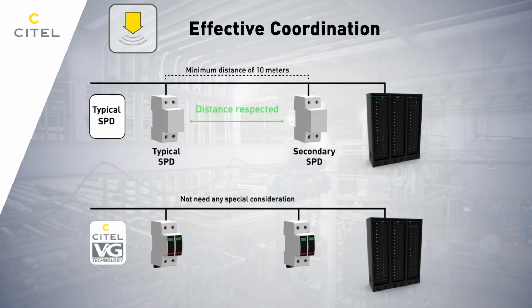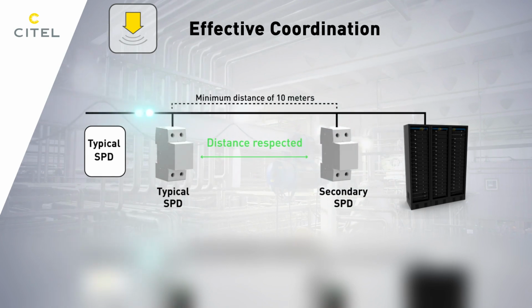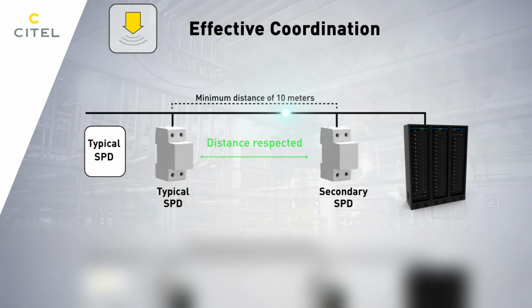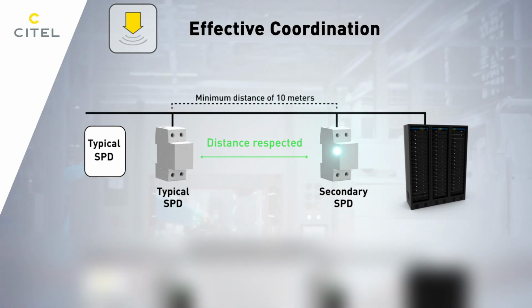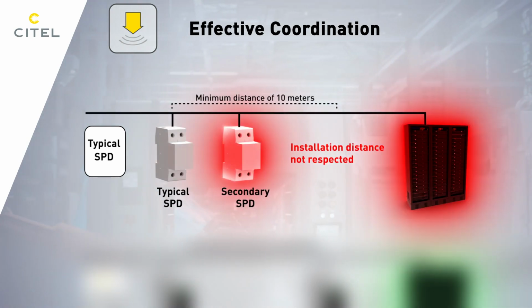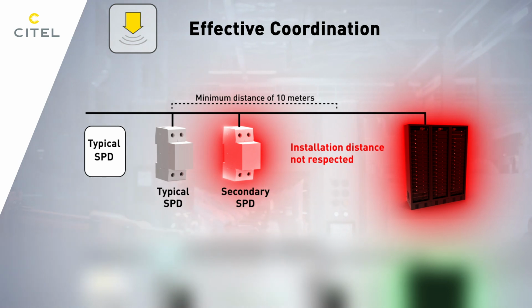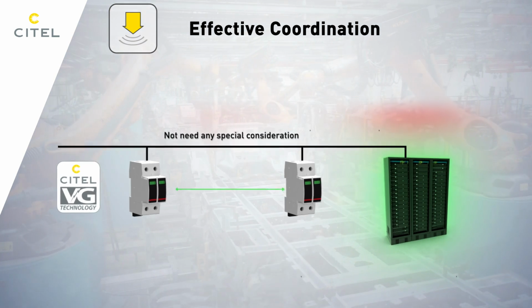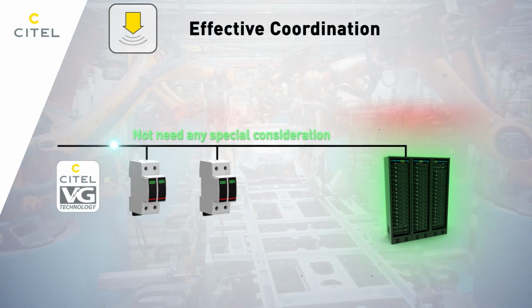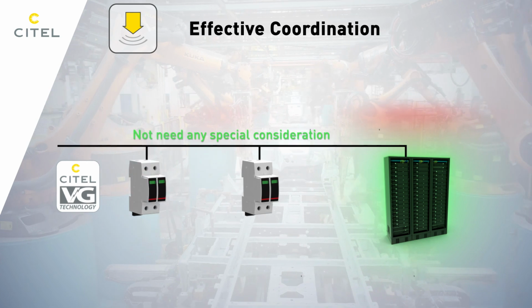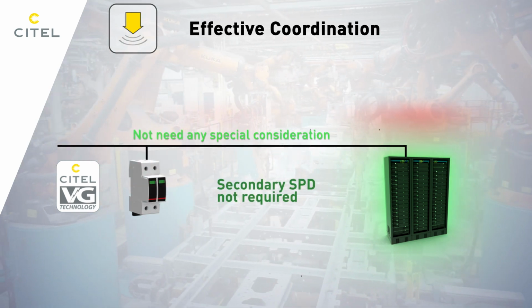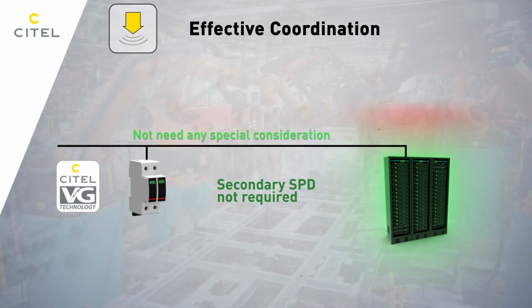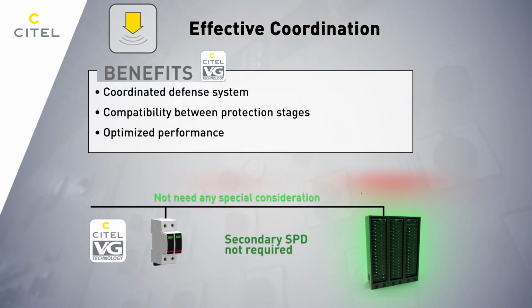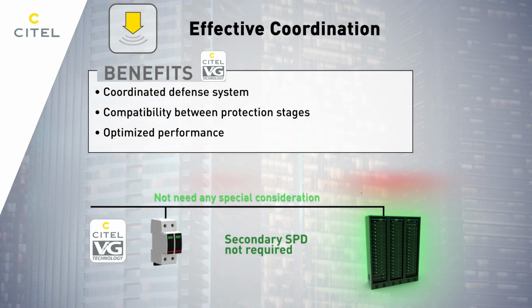Effective coordination is critical to ensure that the initial SPD absorbs most of the surge energy, while downstream SPDs protect the final equipment. While a traditional SPD requires a specific distance between the secondary SPD and the equipment being protected, VG technology removes those requirements, allowing for an easy and efficient installation. No secondary SPD is required, and space conditions are simplified, allowing for safe and effective surge protection without any extra restrictions. Thanks to VG, coordination between SPDs is improved, delivering a coordinated defense system, perfect compatibility between protection stages, and optimized performance across the entire electrical system.